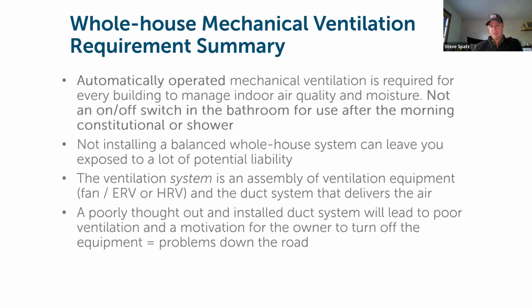The key takeaway here, though, is that this needs to be designed as a system. The ERV or the HRV is just a fancy box in and of itself. You really need to have a well-designed and well-functioning duct system, with the ability to adjust it, attached to that piece of equipment.